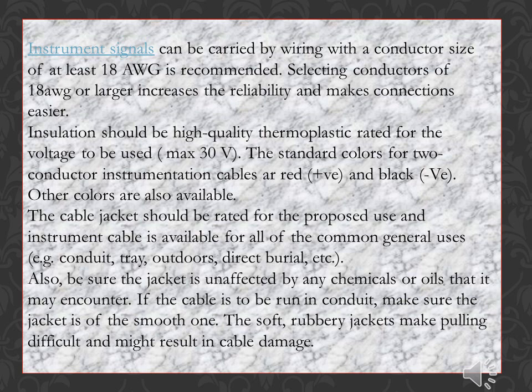Instrument signals can be carried by wiring with a conductor size of at least 18 AWG, which is recommended. Selecting conductors of 18 AWG or larger increases reliability and makes connections easier. Insulation should be high-quality thermoplastic rated for the voltage to be used, max 30V. The standard colors for two-conductor instrumentation cables are red (positive) and black (negative); other colors are also available.